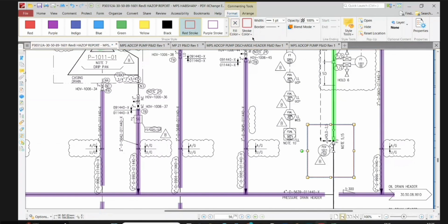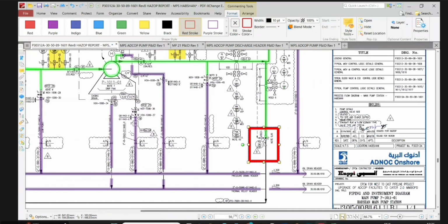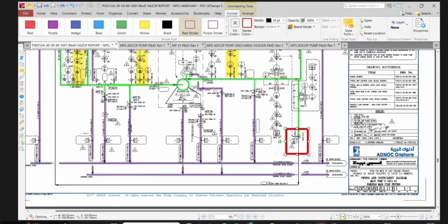No, but for PALL, the demand comes when the recirculation is not properly happening. If this is happening, then the PALL demand will not come. Ultimately, if something goes wrong at pump suction, PAL will come, FAL will come, and this will try to open the recirculation valve, and this will ensure that the pump doesn't starve. So this is the safety mode. So we have to take credit of this FCV.